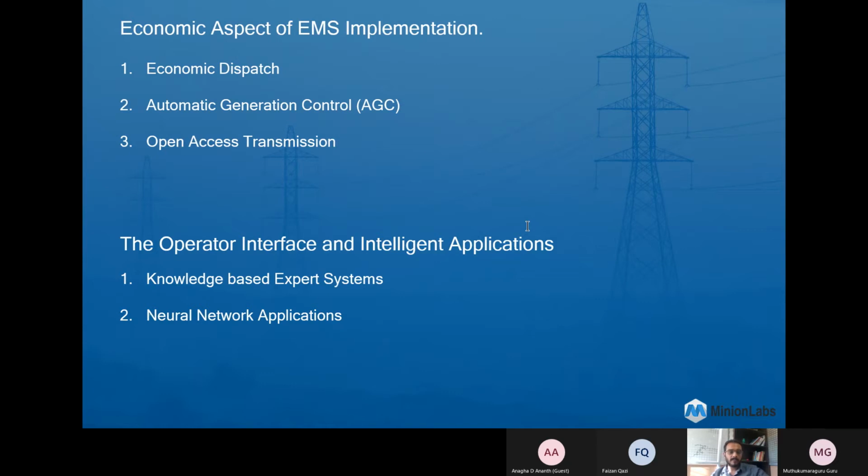Expert systems are also very powerful at solving diagnostic reasoning problems. Therefore, many EMS include expert systems to diagnose faults on the power system using status, switch status, and relay target information. This process is made even more powerful when a model of the power system is built from the SCADA system database, because the SCADA system contains all the diagnostic fault information built in already.